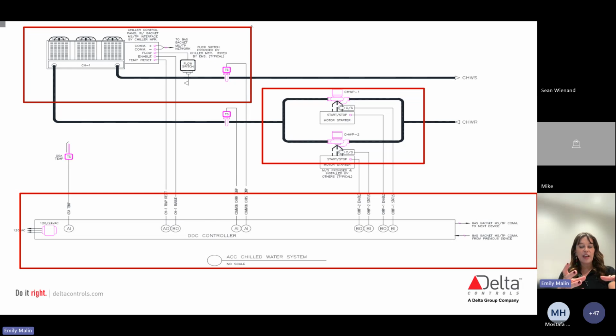So from a diagram like this, combined with our points list, we can really start to build in what we want this system to look at. So again, you see here, we're using an MSTP protocol. We're seeing that we have three analog inputs, one analog output, three binary or digital outputs, and two binary inputs. So essentially what we would need for a system like this is a controller with at least 5 inputs and 4 outputs that are all real, can be wired up to that controller. So really here you could be using, again, anything except for an application specific controller. So you could use a building controller, you could use an advanced application controller, but that application specific wouldn't really work in this scenario.